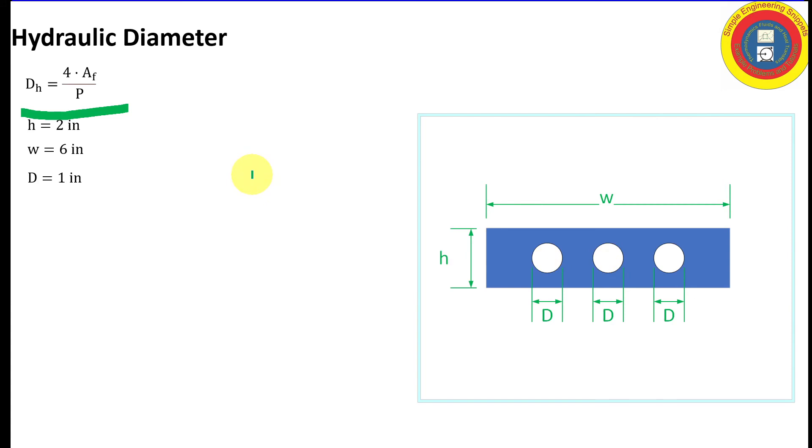So with that let's calculate the flow area. The flow area is the entire flow area of the rectangle minus the area of each of the three tubes. And so this is given by this equation where we have the flow area of the entire rectangle and we subtract from that the flow area of the three internal tubes. Plug in the values and units and we get that the flow area is 9.64 inches squared.